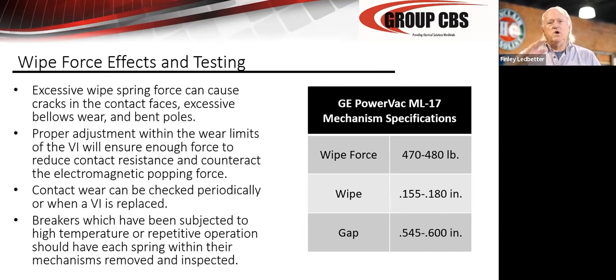And as long as the breaker is within wear and you're under 3,000 operations, very seldom do you see a wipe spring problem. This is what we're talking about. When you get beyond 3,000 operations, the wipe springs are the sort of things that have to be replaced.